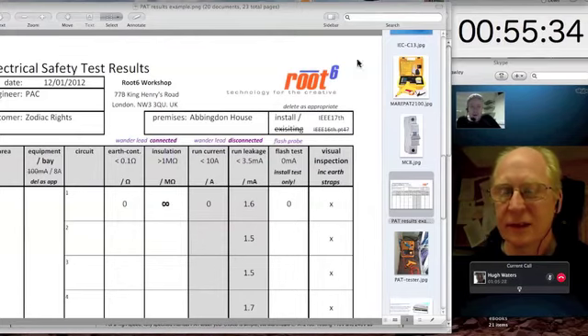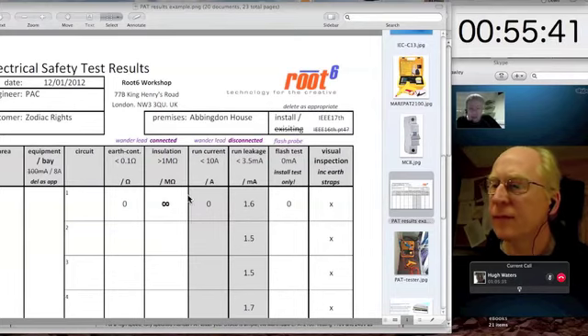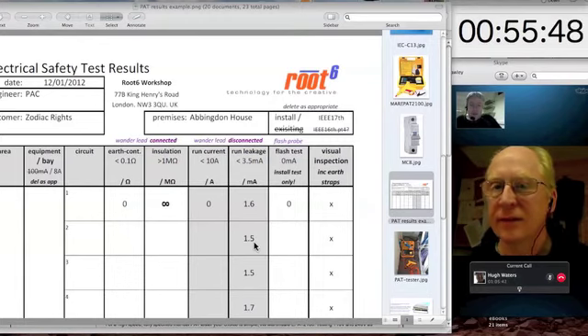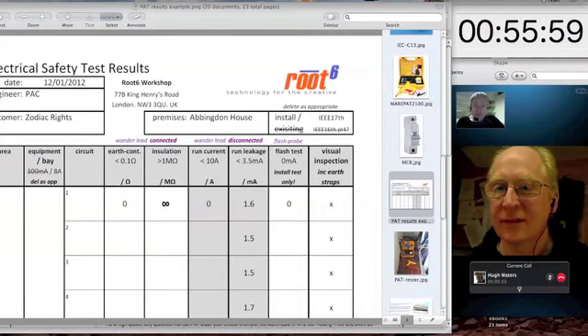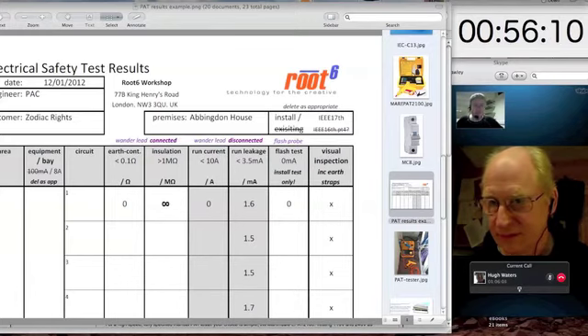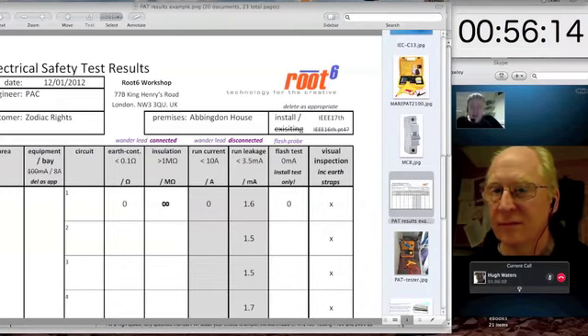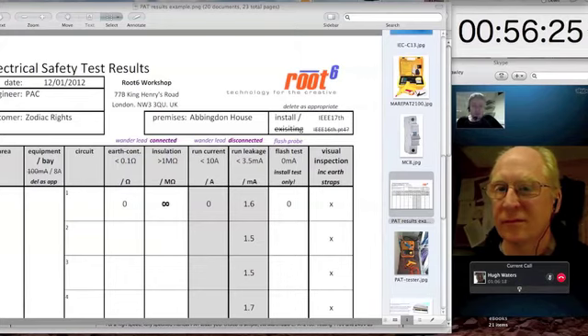And you do see some earth leakage within a cabinet. So these results here, which I think were from a job we did just a couple of months ago, this is real life stuff, just a bit more than a milliamp, and that's well within the spec. Now there is one big systems integrator who will remain nameless, who manufacture their own mains distribution strips. And in fact, they're manufactured in the Far East, and they're manufactured very cheaply because the live, the neutral, and the earth conductors are all running as tracks on a PCB within the mains distribution block. And with their mains distribution units, even with short length cables on the in and the out of the unit, you get more than 4 milliamps of earth leakage.